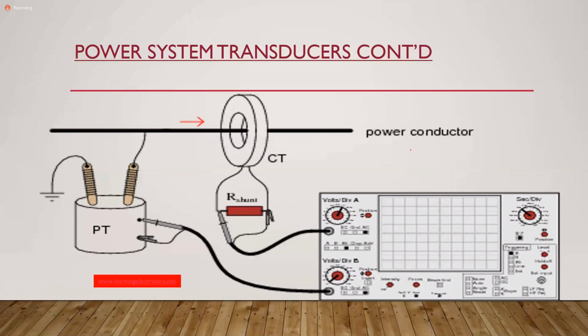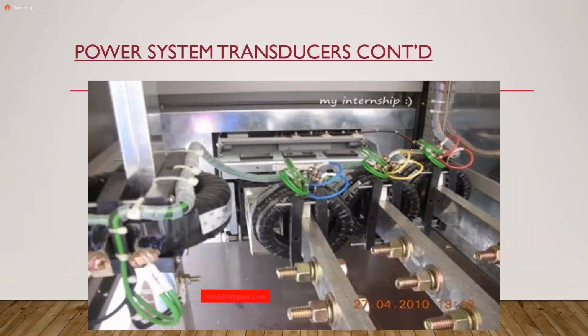In terms of actual, look at your VT, your CT. So what you have, these are your CTs here. All right. So those are your CTs. These would be your bus bars. So what we are showing here would be an industrial setting. So those bars, or these bars rather, those would be your 3 bus bars. Obviously, it's a 3-phase system. And so you have the CTs here, and the bus bars pass through them. So it means that the feed or the supply to this facility would all pass through your CTs.